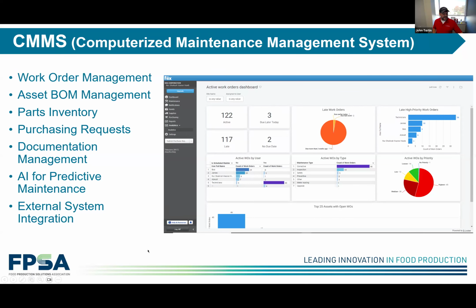It's going to do things like looking at historical detection device profiles to see what that vibration profile looked like, for example. We're beyond the time of just setting high and low limits for different devices. Now you have an AI engine constantly looking at signals like that vibration, looking at events that occurred, what the vibration level was historically before I took this motor out of service. I don't have to explicitly control those parameters for every device on the plant floor anymore - the model is learning that for you over time and becomes more prescriptive the bigger the data set you end up building.